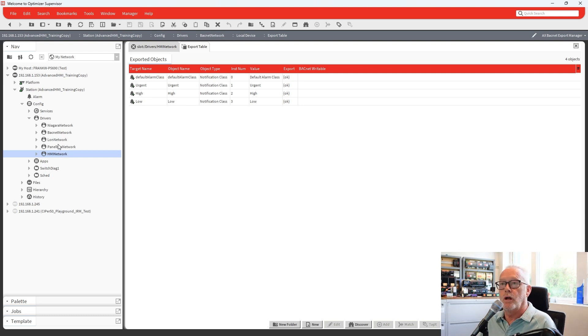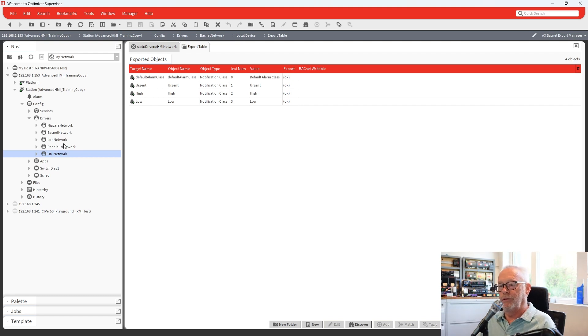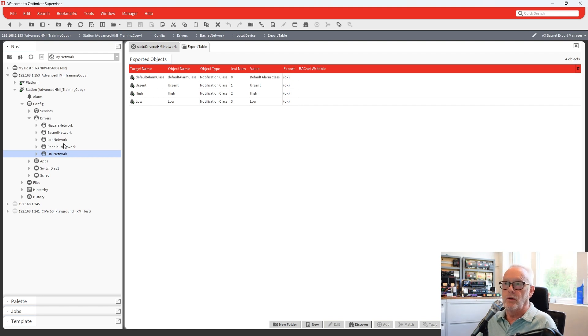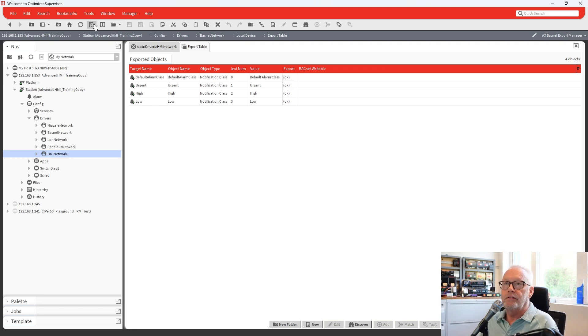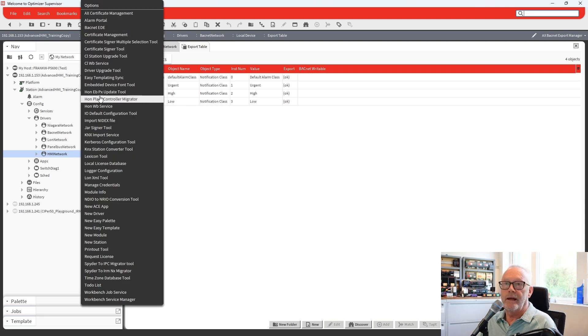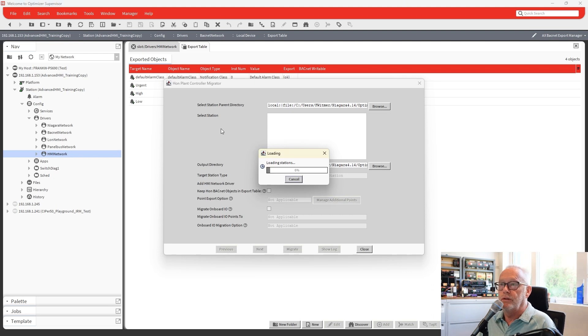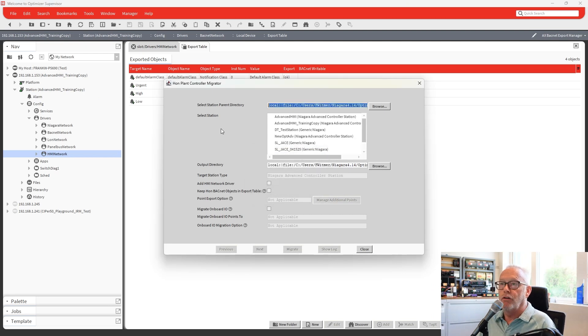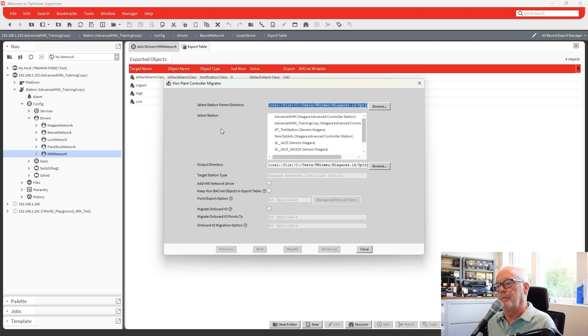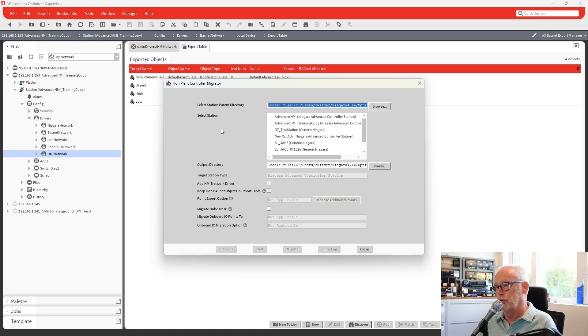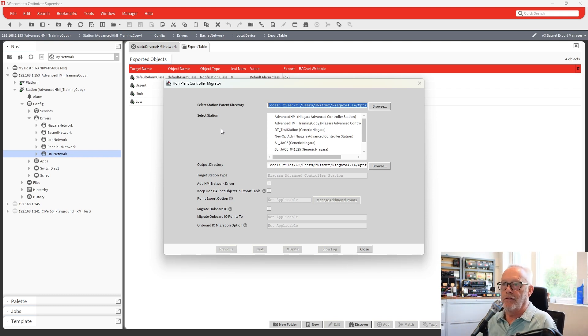Now, if you were to upgrade your 4.13.2 or your previous version of Optimizer Advanced to 4.14.0, you will break the HMI and it will no longer work. And you'd have to leave it all out of there and then start over again. But what they've done is they've added under tools, there is now a HON plant controller migrator. And what that allows you to do is migrate the previous version of your station and migrate it up to 4.14.0 with the new structure and having a separate HMI network and also updating for using the user passwords instead of having a PIN number. All that's done within this migrator. It takes care of that for you.